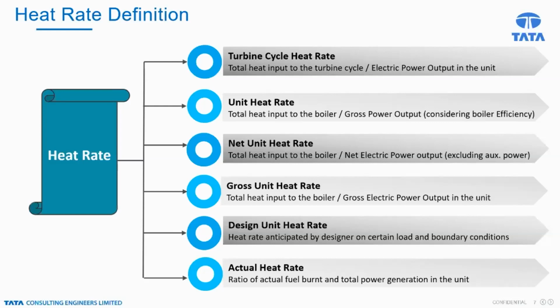Sometimes people take the turbine cycle heat rate by mistake for the unit heat rate, so it is important to know the difference. Excluding the boiler is the turbine cycle heat rate. If we include the boiler efficiency, it is the unit heat rate.